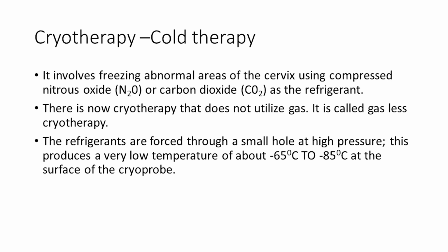I'll quickly mention cryotherapy. Cryotherapy, also known as cold therapy, involves freezing the abnormal area of the cervix, the TZ, with compressed gases, either nitrous oxide or carbon dioxide, as the refrigerant. That means the gas is forced out through a small nozzle and causes freezing of the cervix when the probe is applied to the cervix. The refrigerant is forced through a small hole at high pressure. This produces a very low temperature of about minus 65 degrees at the surface of the probe.